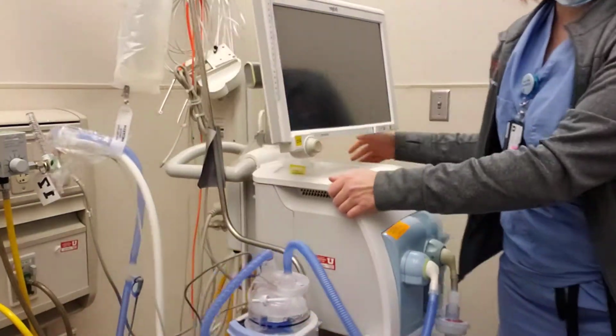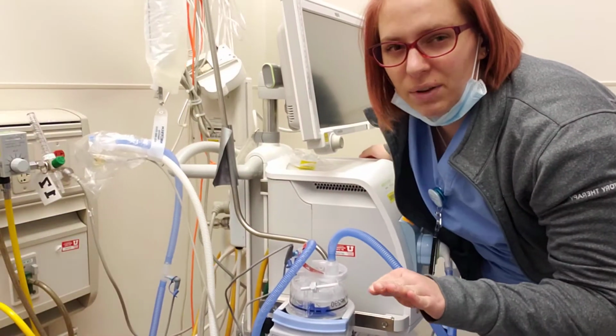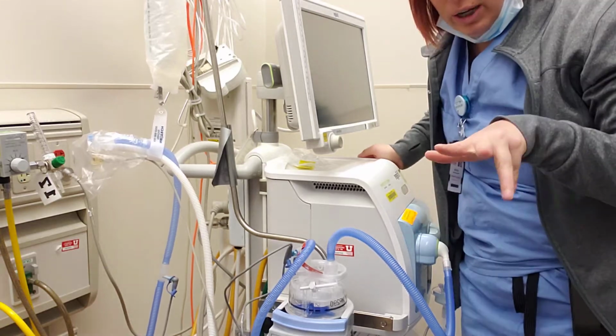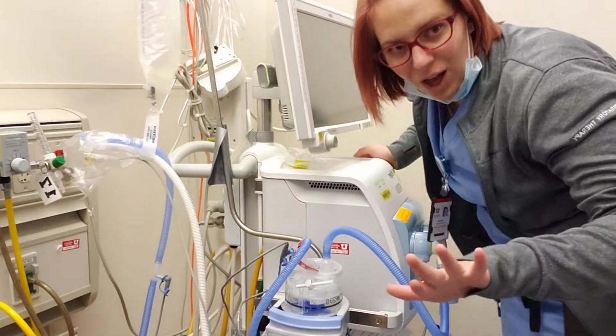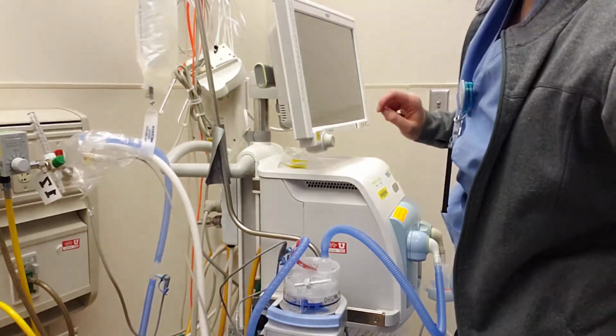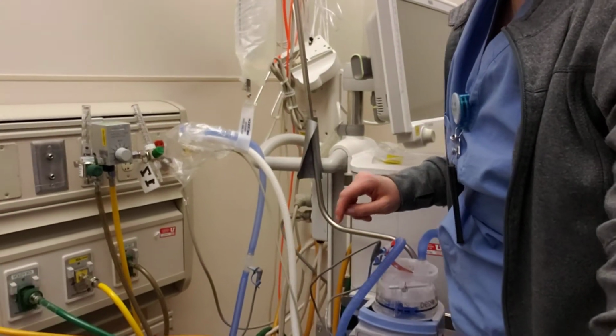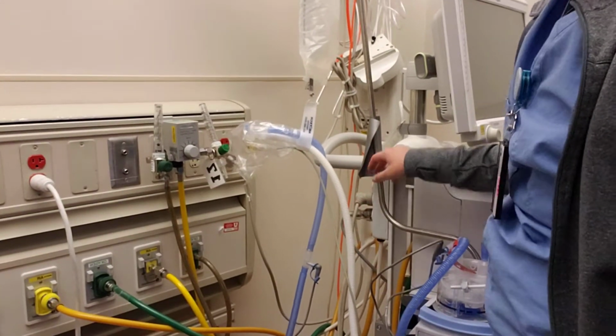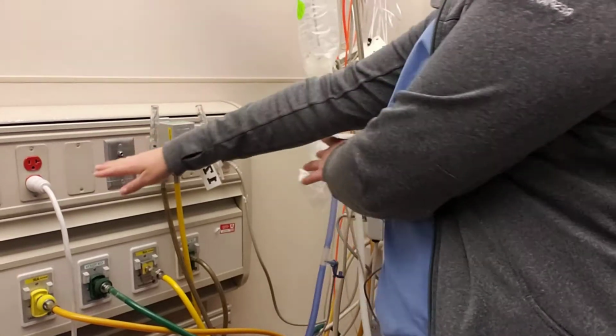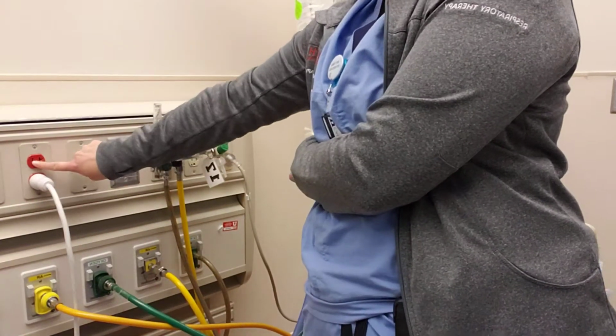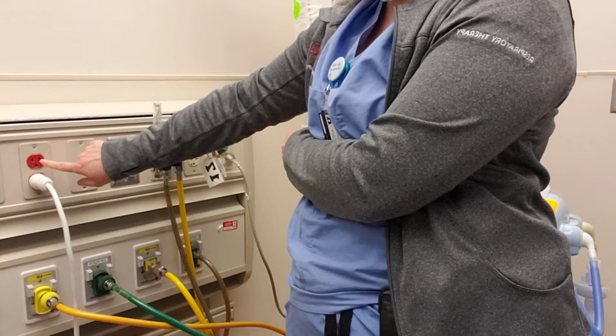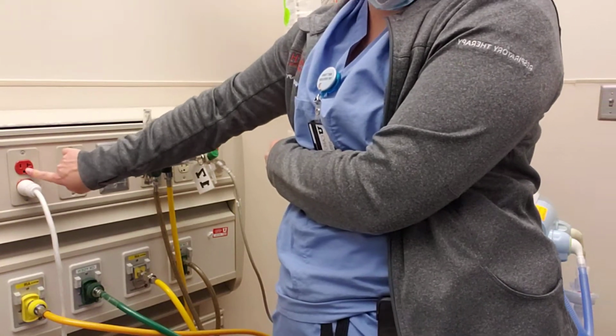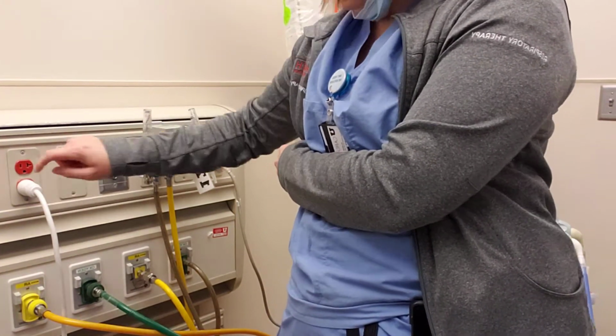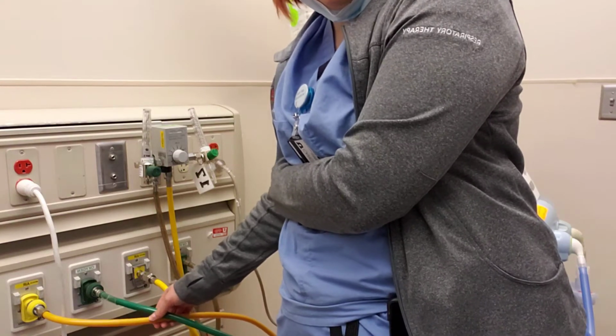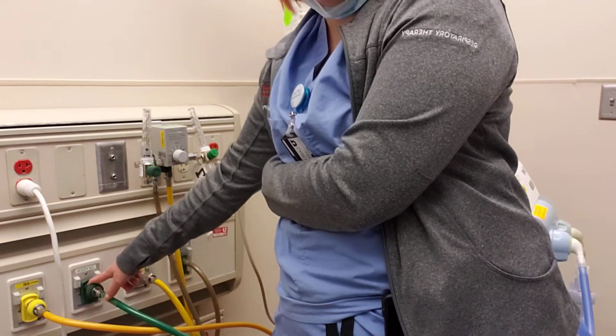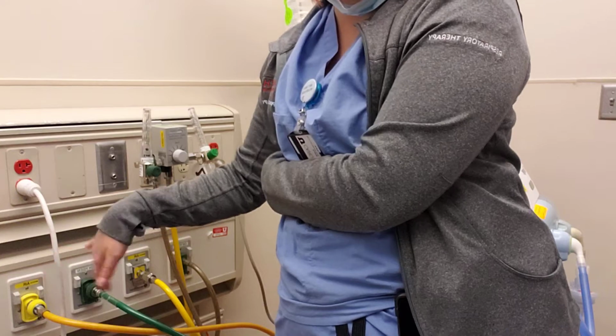Let me apologize in advance, I'm going to be moving the phone camera a lot, so if you guys get a little dizzy. Again, as with any mechanical ventilator, we are using this for ventilation, so make sure it is plugged into a red outlet. We electronically and pneumatically run, so you do need a gas source of both air and oxygen at 50 psi.